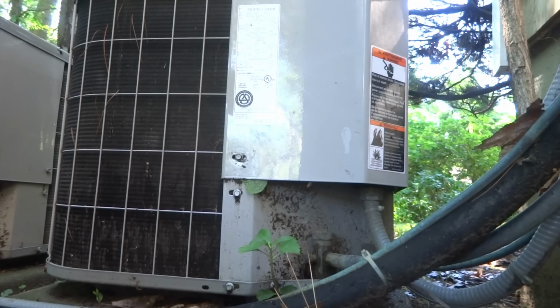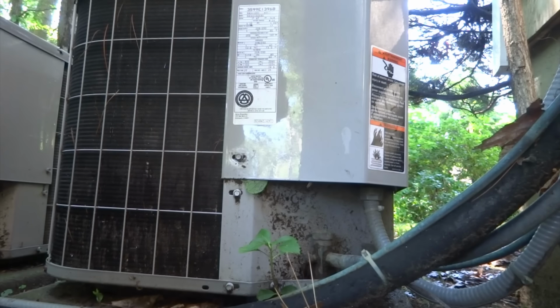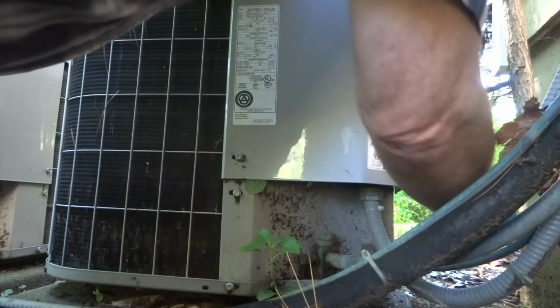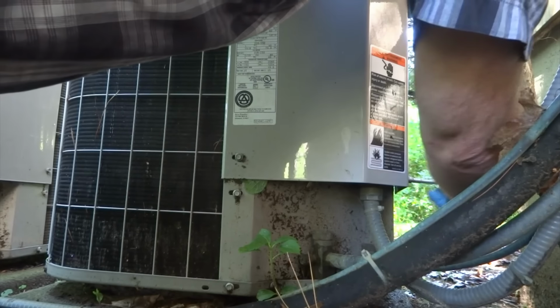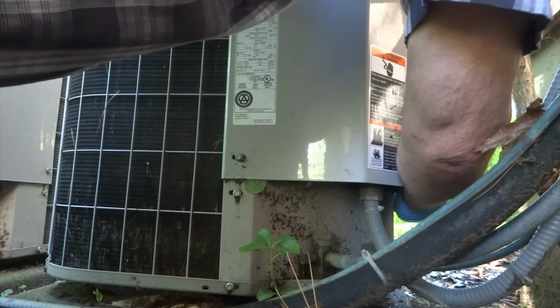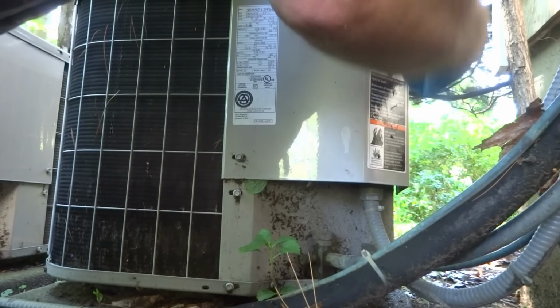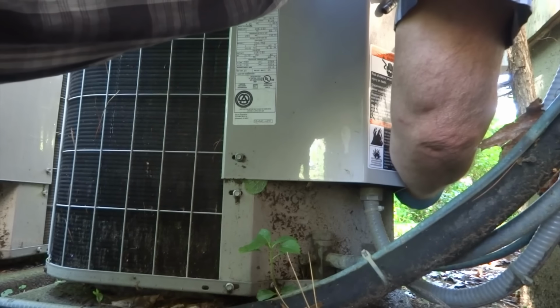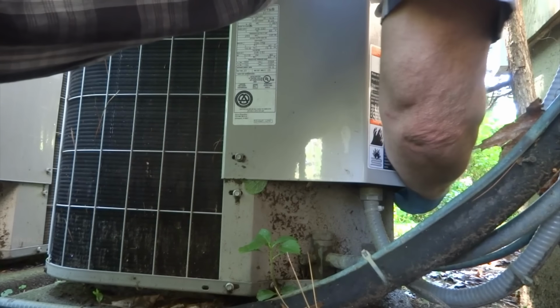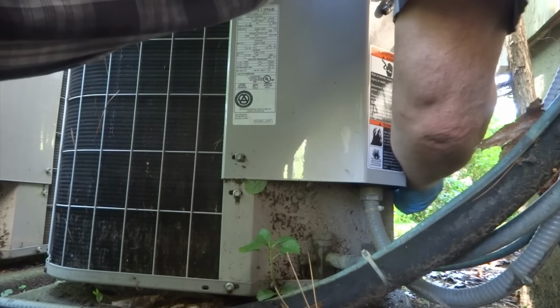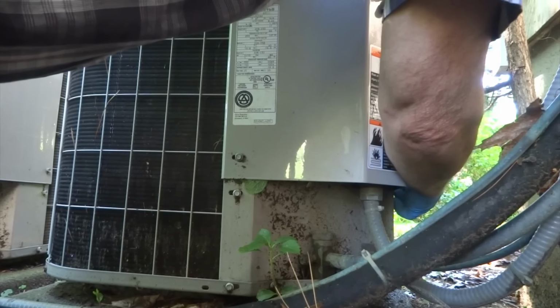So the air handler was running, but this wasn't kicking in. Correct, that was the initial problem, and then I was moving stuff around. We had Mass Save come in, and they put in a new thermostat, but they didn't move the AC wires over to the new thermostat. Maybe the thermostat's not wired right. Yeah, it could be as simple as that for the air handler. But when the guy went up into the attic, he said he could smell some burning.